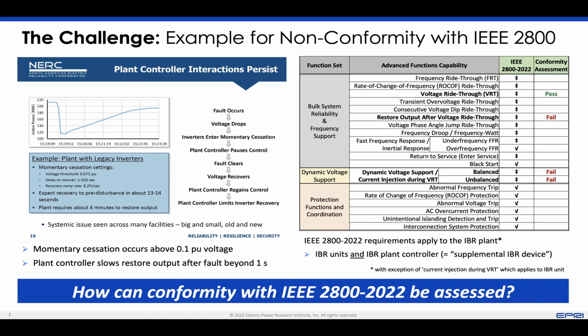So that's where it failed. Even during the fault, instead of providing short circuit current, whether balanced or unbalanced, depending on the type of fault, this plant went into momentary cessation at a level of retained voltage much higher than the permitted 10% per IEEE 2800.